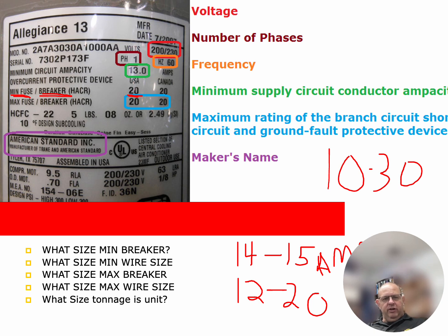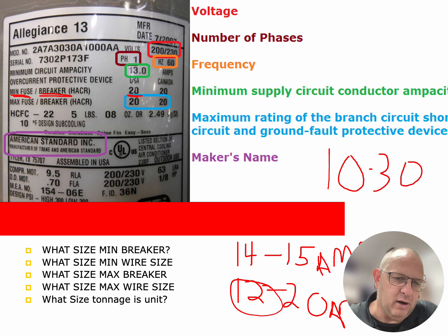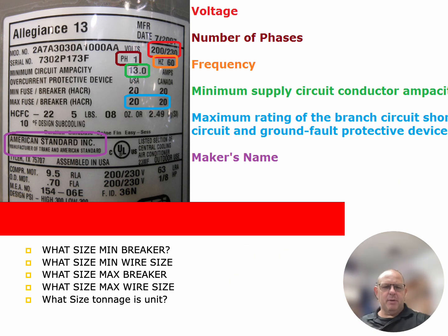So when I ask you, and the data plate tells us that the minimum breaker that can be installed on this system happens to be a 20 amp breaker, well, what size wire do I have to run for a 20 amp breaker? I go back to the NEC, and the NEC says for a 20 amp breaker you have to run a 12 gauge wire. So the answer up here is the minimum circuit breaker is a 20 amp, and I have to run a 12 gauge wire. Okay, next question that we need to ask ourselves is what's the maximum breaker that I can install on this particular unit? And the maximum breaker that I can install on this particular unit happens to be, because of the nameplate that's at the top of it, a 20 amp breaker. Well, what is the minimum size wire that I can run for this particular outdoor unit? And it is a 12 gauge wire.